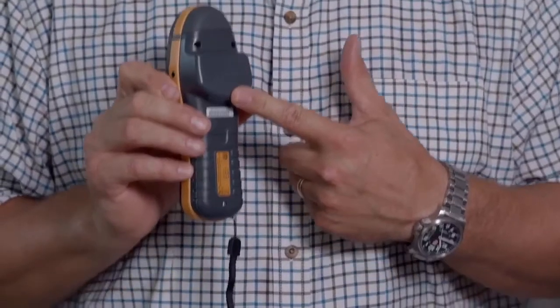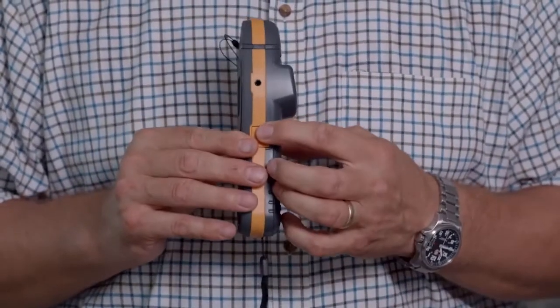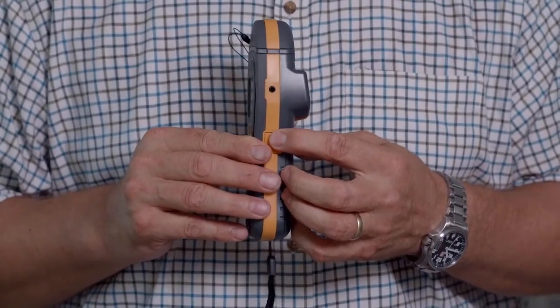This is a dual function moisture meter with both pin type measurement and non-invasive RF measurements. The pins on the top are protected by a cap with a leash. There's also a wrist leash and a silicone front cover. On the back of the instrument you'll see the large flat area for positive engagement for the RF non-invasive mode, and on the side you'll see the port for the accessories.